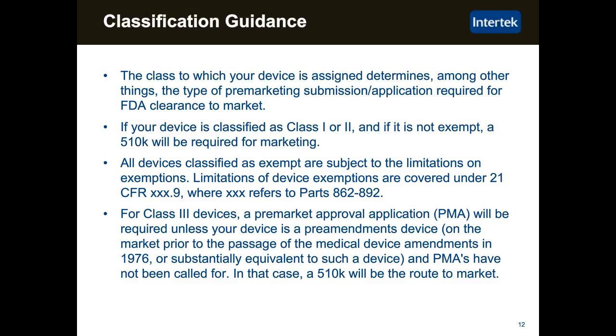For Class 3 devices, a pre-market application or PMA will be required unless your device is a pre-amendments device, and that means it was on the market prior to 1976, or it's substantially equivalent to a pre-amendments device, and also that the FDA has not moved a pre-amendment device into requiring a PMA. In those cases, though, where what would be a Class 3 device has been determined to be a pre-amendment, you may be able to apply a 510K in order to get to market with that device.